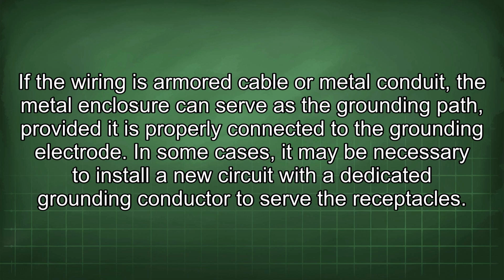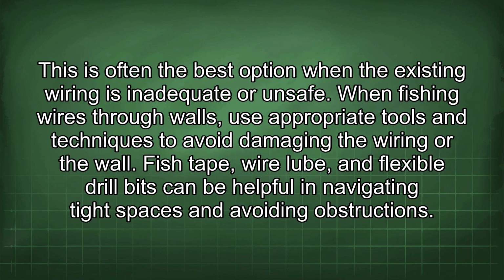In some cases, it may be necessary to install a new circuit with a dedicated grounding conductor to serve the receptacles. This is often the best option when the existing wiring is inadequate or unsafe. When fishing wires through walls, use appropriate tools and techniques to avoid damaging the wiring or the wall. Fish tape, wire lube, and flexible drill bits can be helpful in navigating tight spaces and avoiding obstructions.